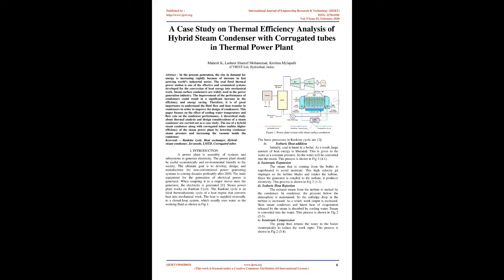Steam surface condensers are widely used in the power generation industry. The improvement of the performance of condensers could result in a significant increase in efficiency and energy saving. Therefore, it is of great importance to understand the fluid flow and heat transfer in condensers in order to improve the design of condensers. This paper focuses on the effect of cooling water temperature and flow rate on the condenser performance. A theoretical study about thermal analysis and design considerations of a steam condenser is carried out as a case study.